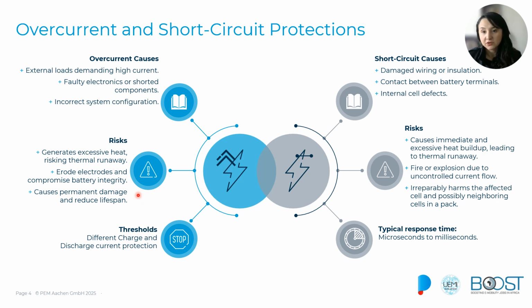The overcurrent protections are then implemented depending on the direction of the flow of current, and different protection levels are used. So we have different levels and combinations between amplitude and duration. We may have, for instance, a very high current and short duration protection, or another level that will be a lower current but longer duration. And all of these will be defined according to the battery specifications.